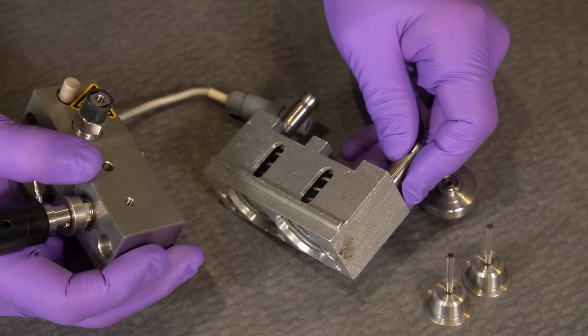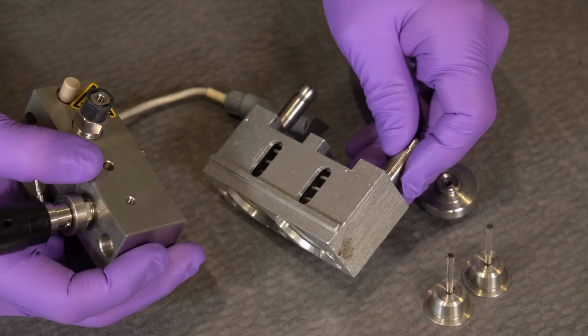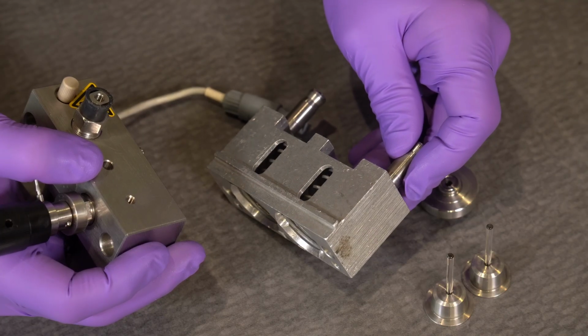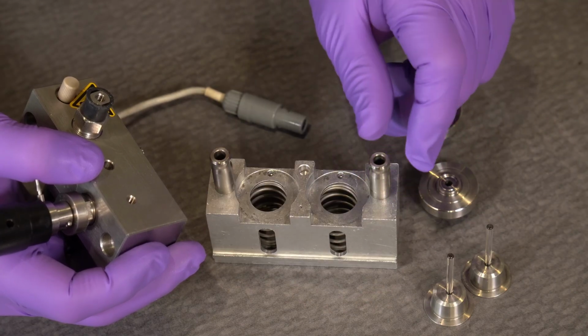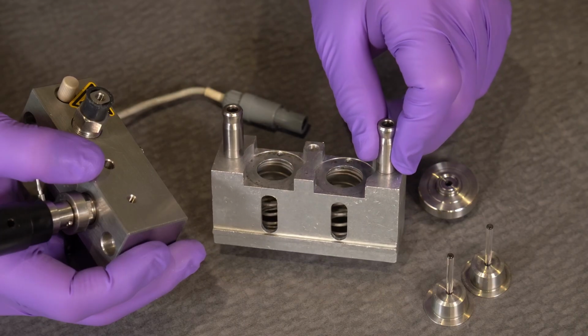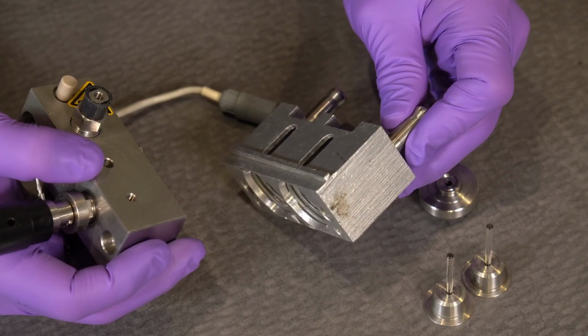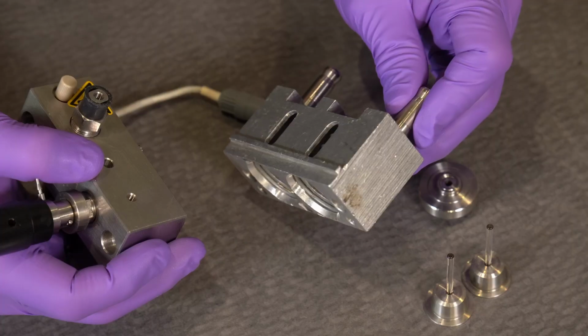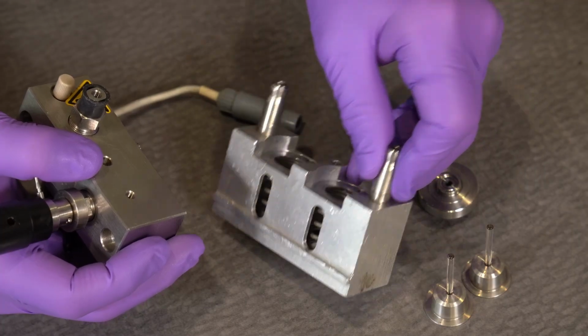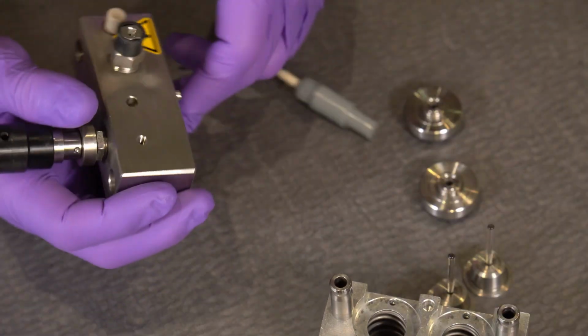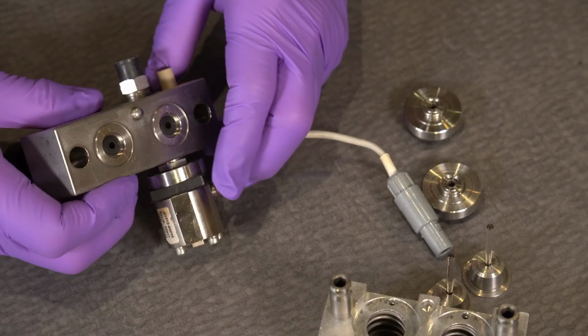If you have leaky pump seals, if they've been leaking for a while and you're using buffers, you'll see some salt deposits back here. That's a sign that you've had a leak. So just take a water squirt bottle and squirt it on there to get rid of the salt deposits. In this case, it's nice and clean, so I don't have to worry about that. And then this is where we're going to find the pump seals.